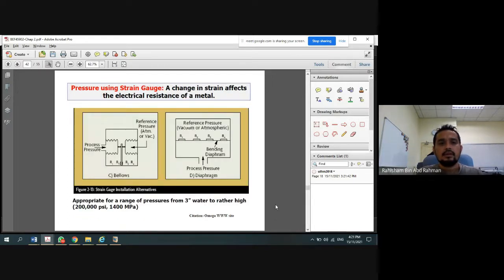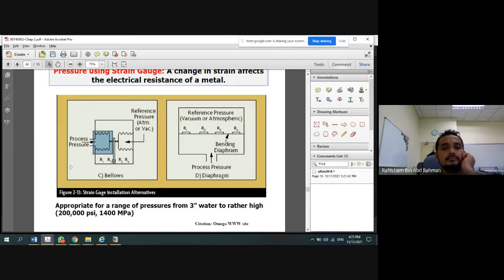Okay, some pressure measurement by using a strain gauge. A change in strain affects the electrical resistance of the metal. Okay, let's see this one. We have a bellows. Okay, we have a pressure. Pressure goes into the bellows, and then we have the pressure based on ATM values. And then this bellows will push away this one, and then this will give a value, a value in terms of electrical resistance. Okay. This one also the same.